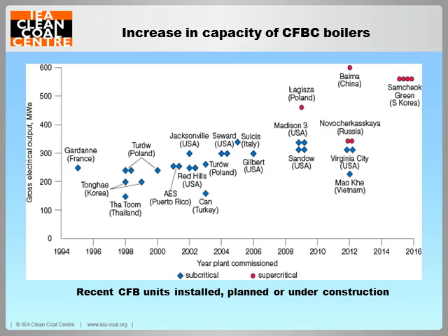And currently, a 600 megawatt supercritical CFBC demonstration unit is under commissioning at a coal-fired biomass power plant in China. This is domestically designed and manufactured by a Chinese company, and it uses Alstom's pant-leg design. Once in operation, it will be the world's largest CFBC boiler. Today, a CFBC boiler with capacity of up to 800 megawatts is commercially available. Further scale-up of CFBC units to above 800 is possible.